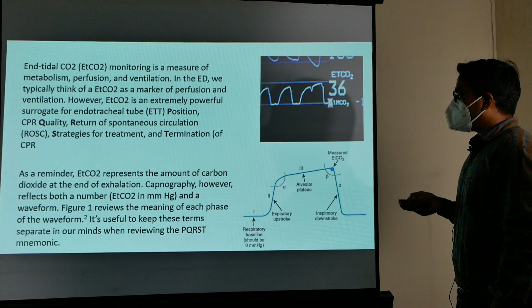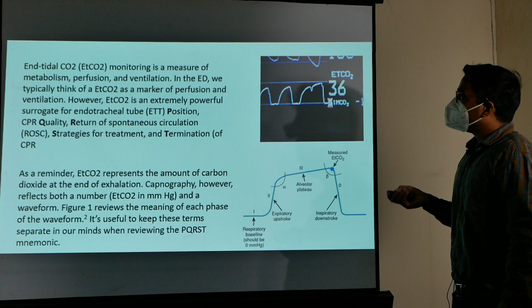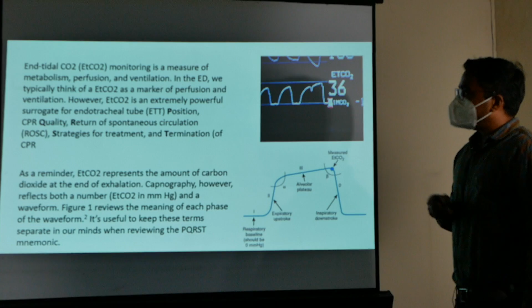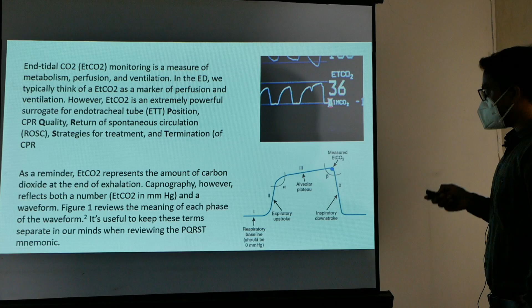Capnography reflects both the number in millimeters of mercury and the waveform. This shows the EtCO2 waveform, and at the end of the exhale it measures the EtCO2. Then the inspiration restarts, which is shown by the down stroke of the inspiration. The normal value of EtCO2 is around 35 to 45, and during CPR it should be more than 20 mm of Hg. If it is less than 20 mm of Hg, say 10 mm of Hg, it means the quality of CPR is not good, and if it is more than 20 mm of Hg, it means the quality of CPR is good.